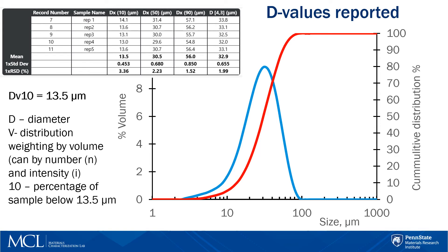For volume-weighted particle size distributions, which are reported by laser diffraction, it is convenient to report parameters based upon the maximum particle size for a given percentage volume. These percentages are reported as D values. For example, DV10 is equal to 13.5 microns. Here, D is diameter, V is distribution weighting by volume, and 10 is the percentage of the sample below 13.5 microns. So it means that 10% by volume of your particles is less than 13.5 micrometers.